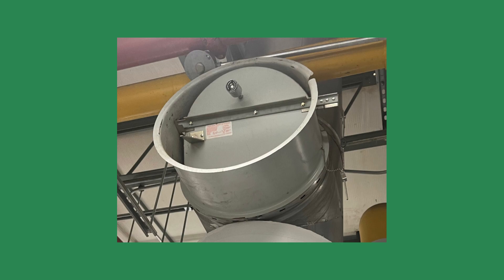One of the most misunderstood components inside a boiler room is the barometric damper, which controls the draft inside a boiler. It is installed on boilers that use a Category 1 vent that have negative flue conditions and are non-condensing.